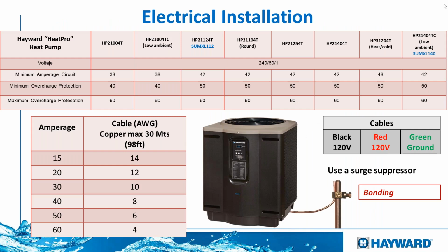If we go to the electrical installation, a couple things I want to mention here. First of all, every single heater has a minimum amperage circuit. Well, every heater is going to require a minimum breaker size or a maximum. So let's do this little example. The biggest heat pump we have, which is 140,000 BTUs, requires a breaker of minimum 50 amps or maximum 60. So you can put either one.